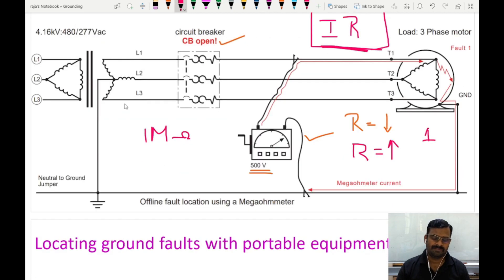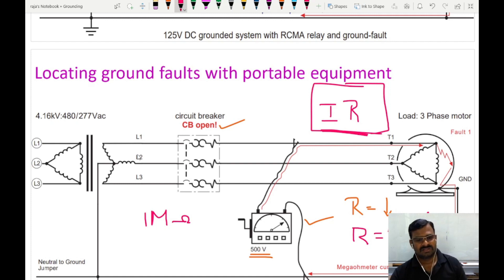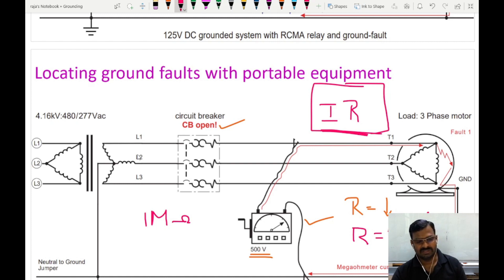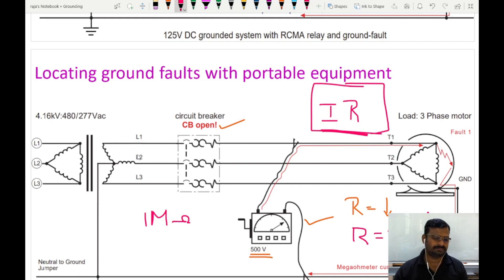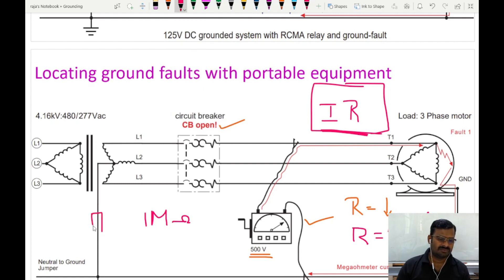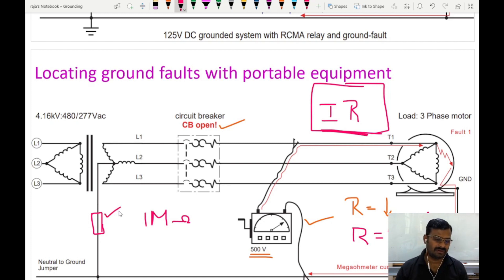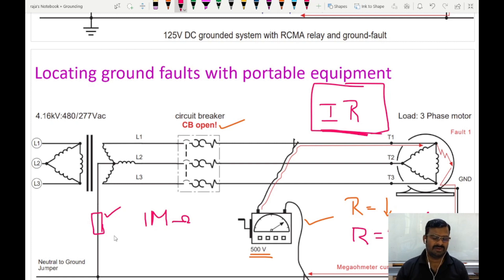Remember: there should be no power while doing this test and the circuit breaker should be in the open condition. To summarize, a solidly grounded system will have very high fault current because the loop impedance is very, very low. Because of this high fault current, there could be damage to the system. To avoid this problem, we can insert a resistance in the ground path, and we will see that resistance grounded system in the next video. Thank you very much — I hope it is clear. If you have any doubts, please let me know in the comment box.